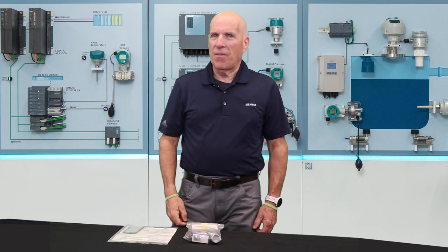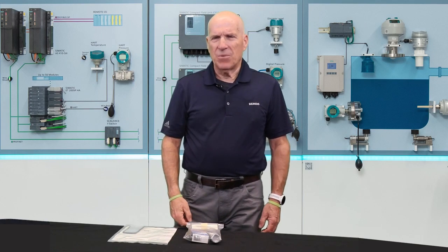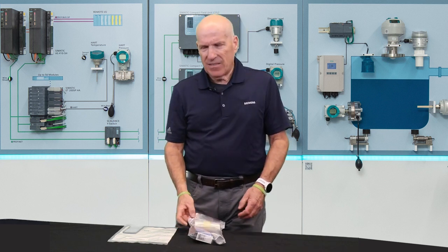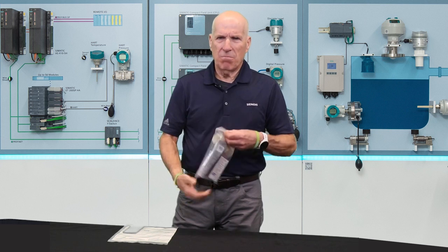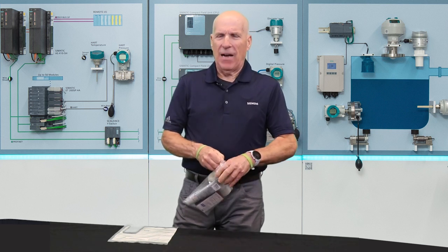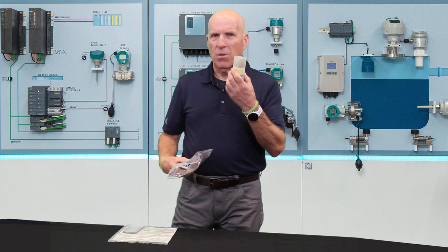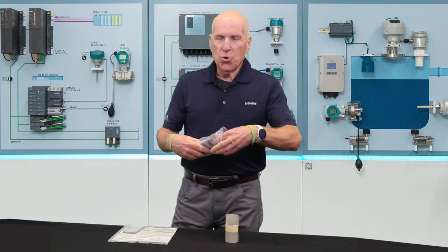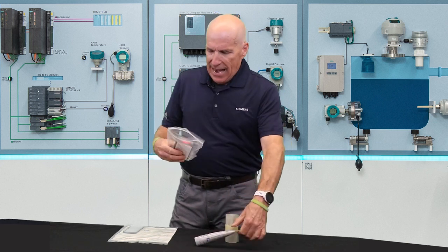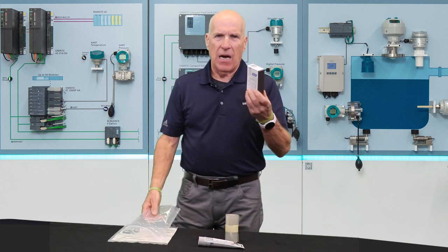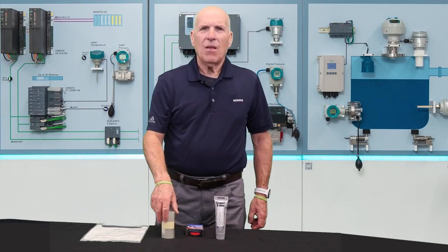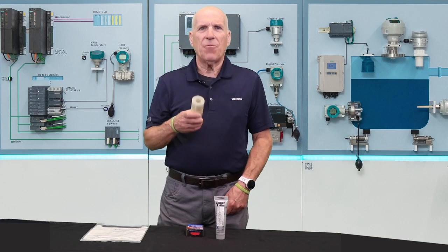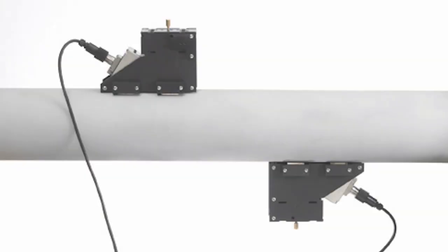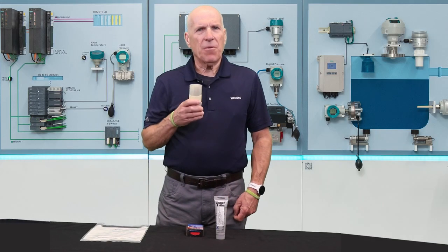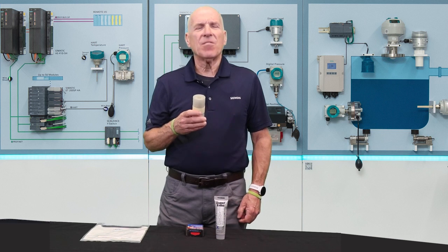In addition to the mounting hardware that we just covered, you'll find a few more items contained within the hardware kit in the accessory pack. These include a number of items for installing your sensors, including a mylar roll known as a mounting guide, a tube of coupling compound, and an ordinary sanding block for cleaning up your pipe. The mounting guide is a tool that's necessary if you'll be installing your sensors in direct mode, where they are on opposite sides of the pipe from each other. The use of this tool and the procedure for mounting flow sensors in direct mount is covered in separate videos.